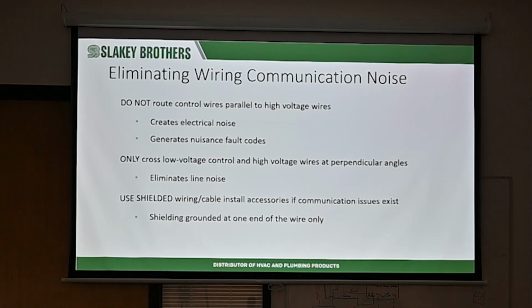Okay. So first thing is, because the communication line is a DC signal, you want to make sure you don't run any of your low voltage line parallel with high voltage. You can run it across. It could be nearby. But if you lay it alongside a lot of high voltage, 115 volts or 208, 230, it will pick up interference and it will really bug you.